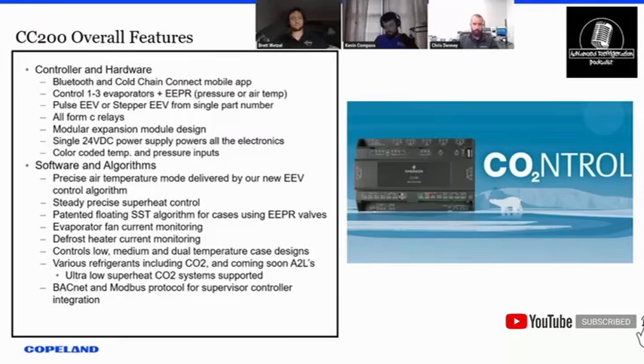Another change up for us is being able to power everything through those side connectors with a single power supply. So if you've ever seen control trays with multiple valve drivers and the main controller, sometimes there's wiring between the main module, like 2 wires for power and 2 wires for comm to hook all those modules together. So if there's space in the tray, you just line these up on the DIN rail and hook them together, and that eliminates 2 points of power, 2 points of comm for each module, cleans up the tray, not having those cables going from module to module. Good little improvement there. We've got some color-coded temperature and pressure inputs to match our sensor insulation color. So that's another handy improvement there on the hardware.